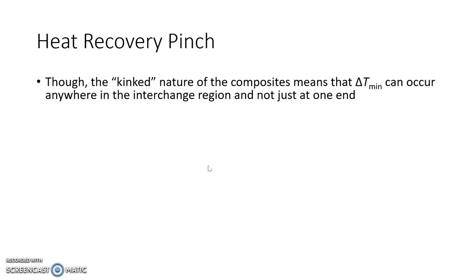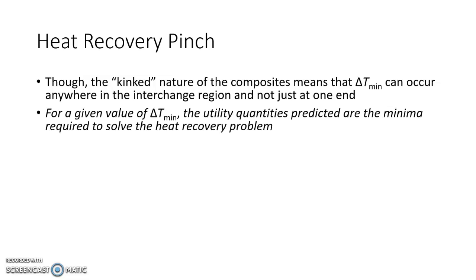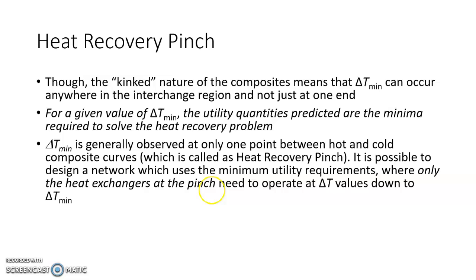So pinch may occur anywhere in the diagram. For a given value of delta T minimum, the utility quantities predicted are the minimum required to solve the heat recovery problem. So once you have identified that there is a pinch, on one side you will find minimum hot utility requirement, on the other side you will find minimum cold utility requirements. Delta T minimum is generally observed only at one point between hot and cold composite curves. This is in general called as a heat recovery pinch. It is possible to design a network which uses the minimum utility requirements where only the heat exchanger at pinch need to operate at a delta T value down to delta T minimum.